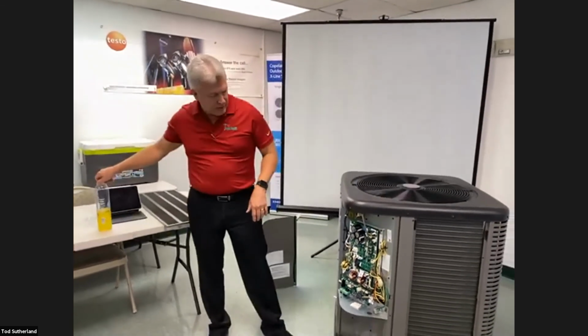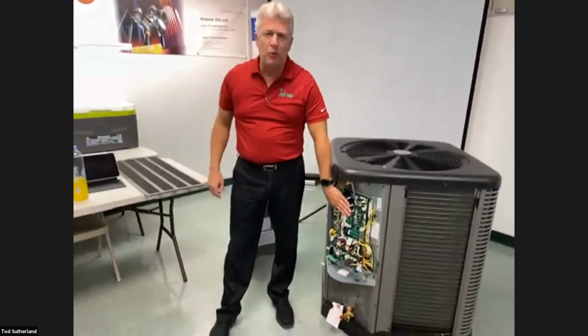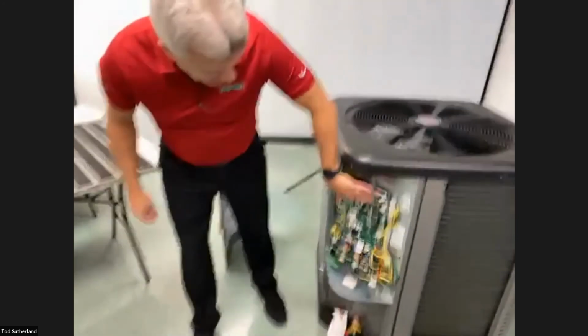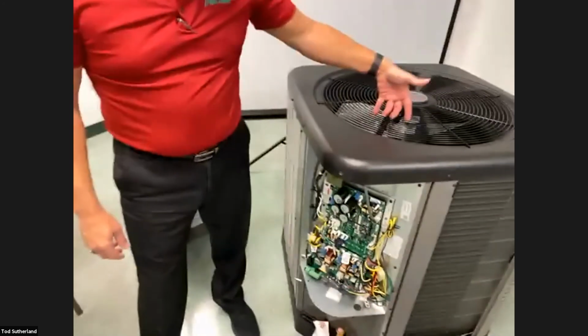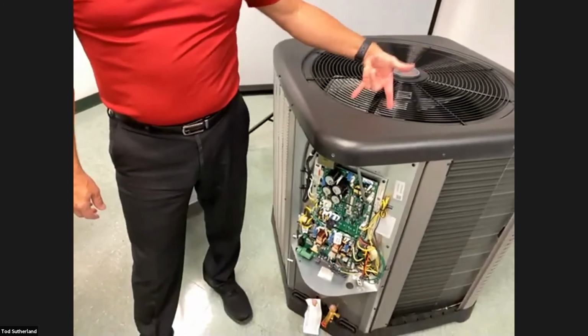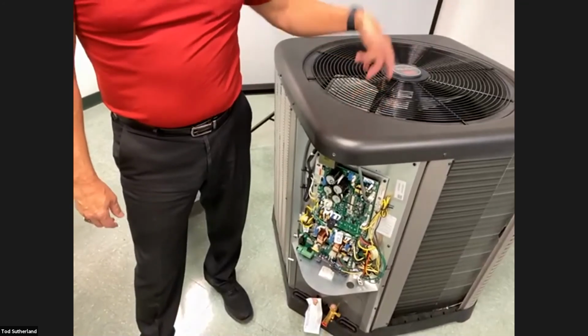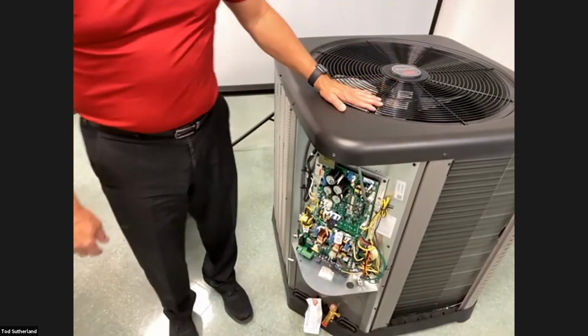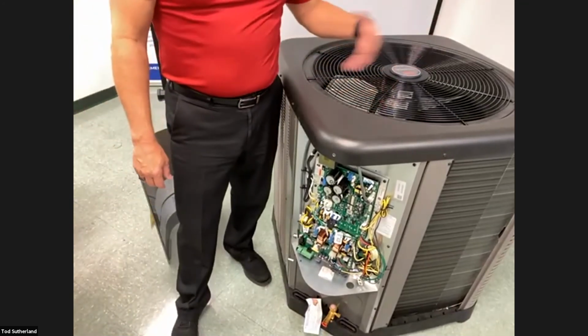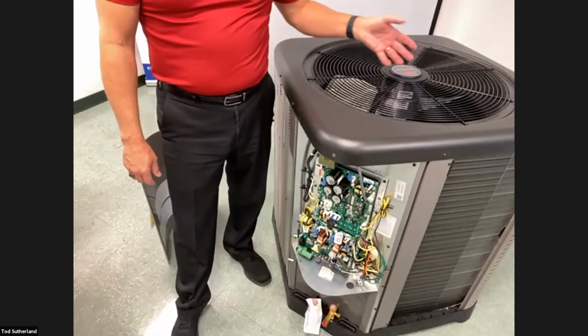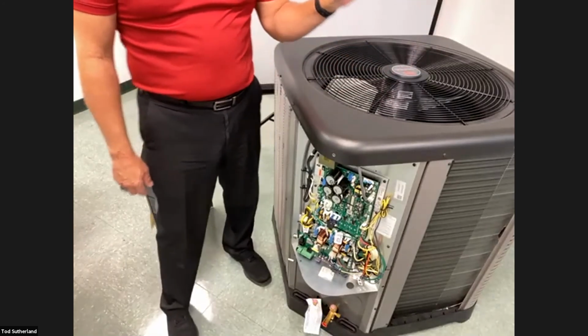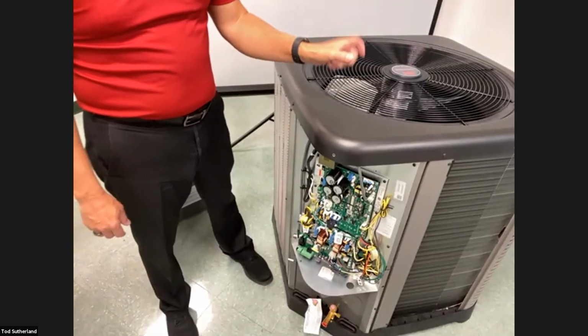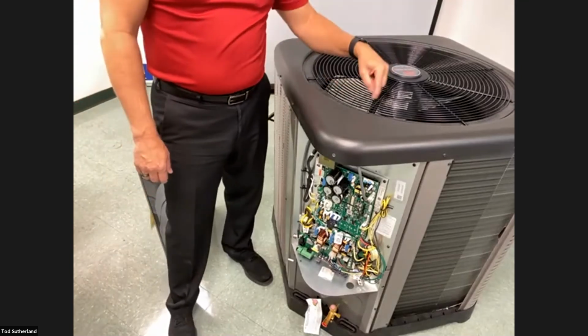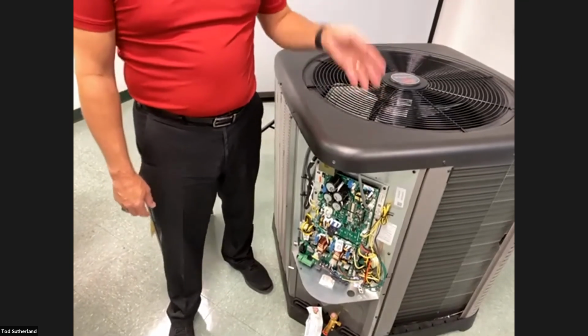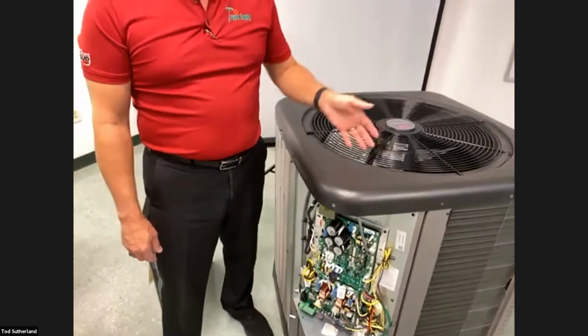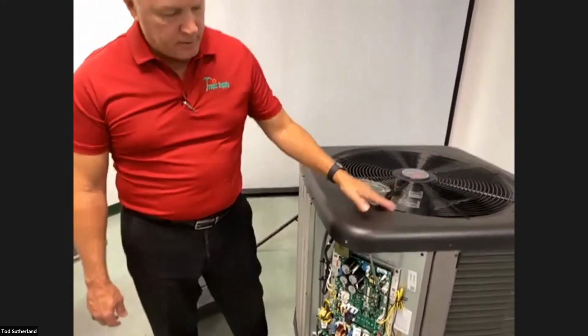One thing I did touch on, the back of this board is a very big heat sink on the back of this entire board inside here. So when you're doing your preventative maintenance on these, you want to make sure you clean that. Don't spray a whole bunch of water on there to clean it. I would rather you use a deep bristled soft brush to brush through that and comb that off of there, just to clean the spider webs, the cobwebs, the mud daubers, whatever else is getting in there to block that up.